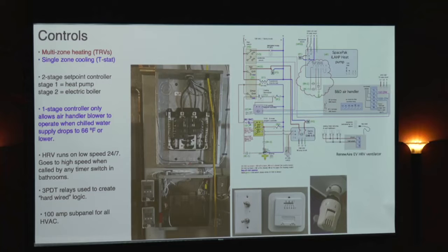You don't need to turn it off. And that way, the TRVs are always able to fine-tune the temperature in each room. There's always flow during the heating mode operation. When you turn the switch to off, it just turns that pump off. So pretty simple. Here's one of the TRVs. Here's the two mode switches.